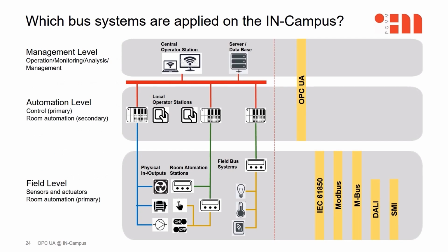If we compare this with the architecture of the building automation system for the INCampus, we can see that the principle of 3 system levels consisting of field, automation, and management level is retained. However, it can also be seen that the system is limited to selected field bus systems and that OPCUA is used as the communication system for the automation and management level.